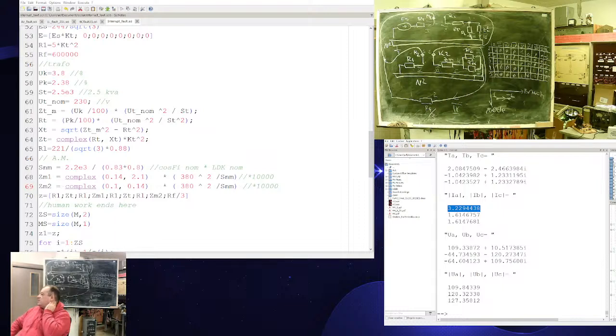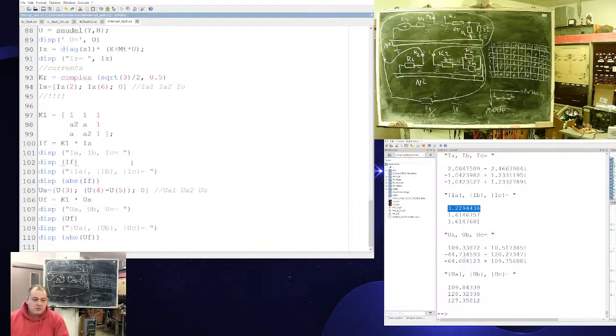If I go upward, I will get primary currents. Let's check what I'm doing with primary currents. To get the primary currents, this one goes, this should be rotated by, and this should be divided by. I would like to make a simple check. Will I get a 0 in phase A in current? No, I'm not getting it.